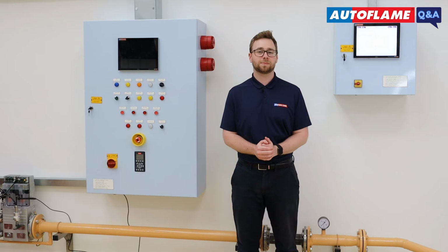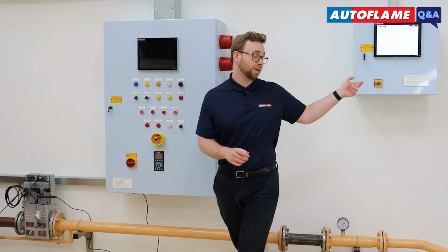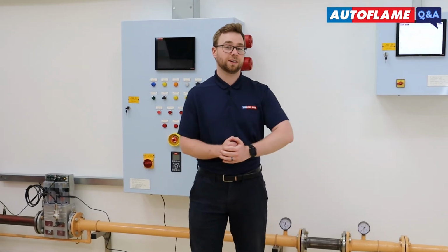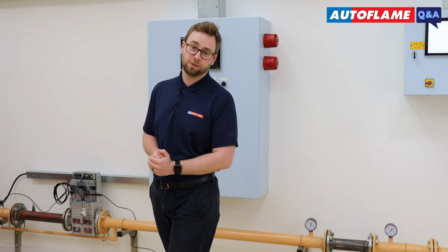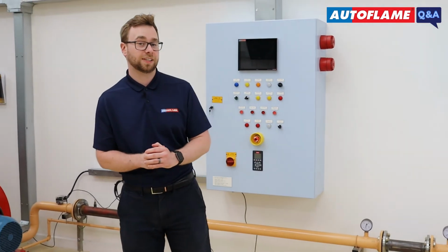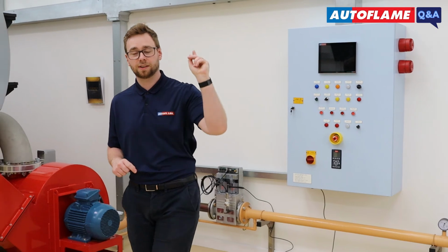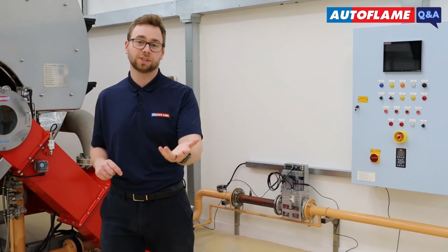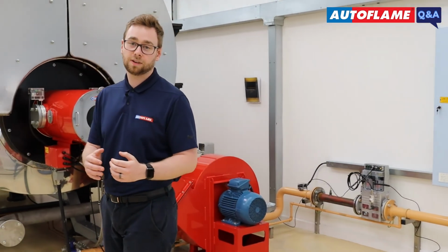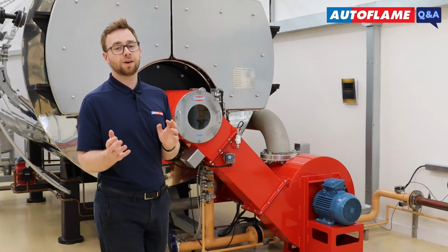Up to 10 Autoflame gas and air pressure sensors can be wired into the Mark8 data transfer interface, or DTI, for the purpose of pressure monitoring and proving. For example, you could use a gas pressure sensor to monitor multiple points on your gas train, maybe the gas pressure coming into the boiler room. You could use an air sensor for your boiler room ventilation, or use any of the sensors for non-boiler related equipment.